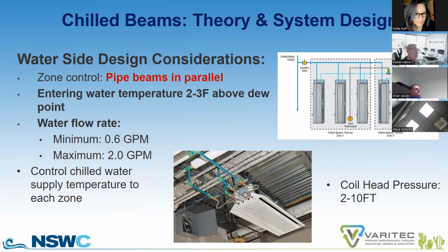Active chill beams or even passive chill beams will be designed to a flow rate between 0.6 and 2 GPM. So you need to control the amount of chill water flow to each zone. I did have a chill beam job compromised on one occasion because the design team inadvertently put a modulating valve at every chill beam. That is not required. You need 1 modulating valve per zone.